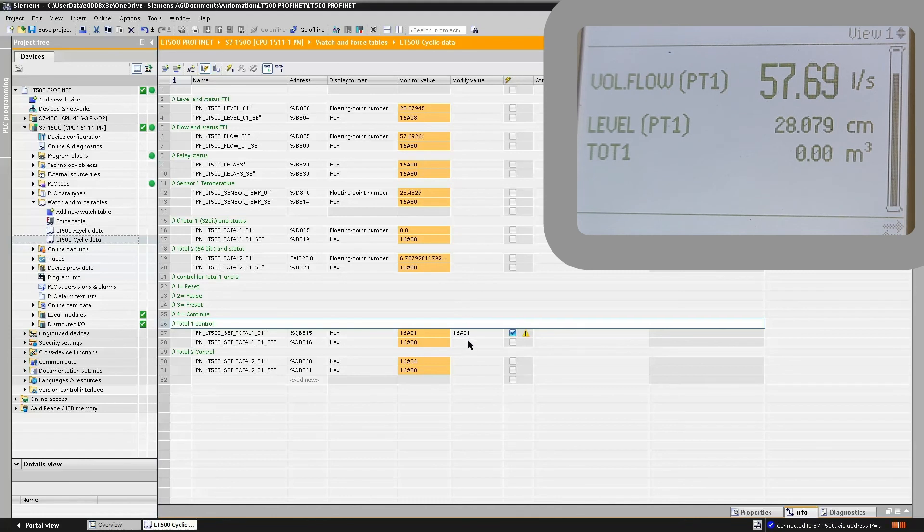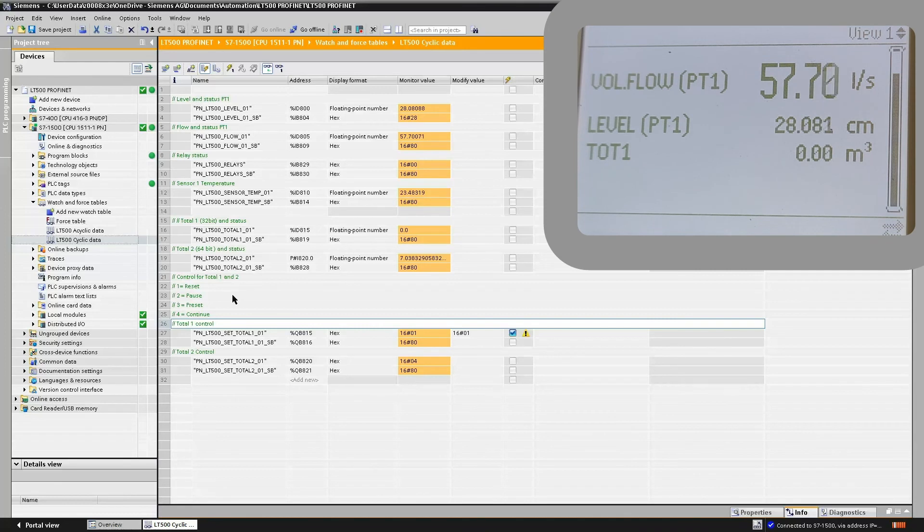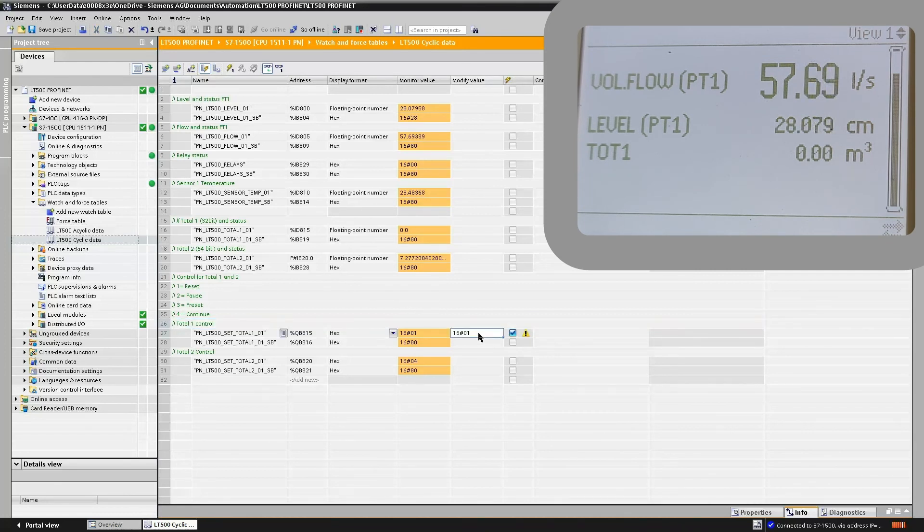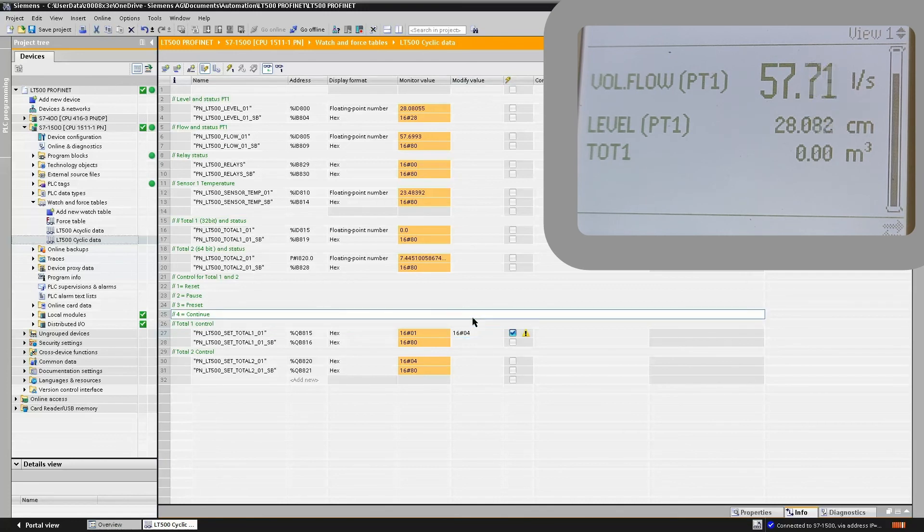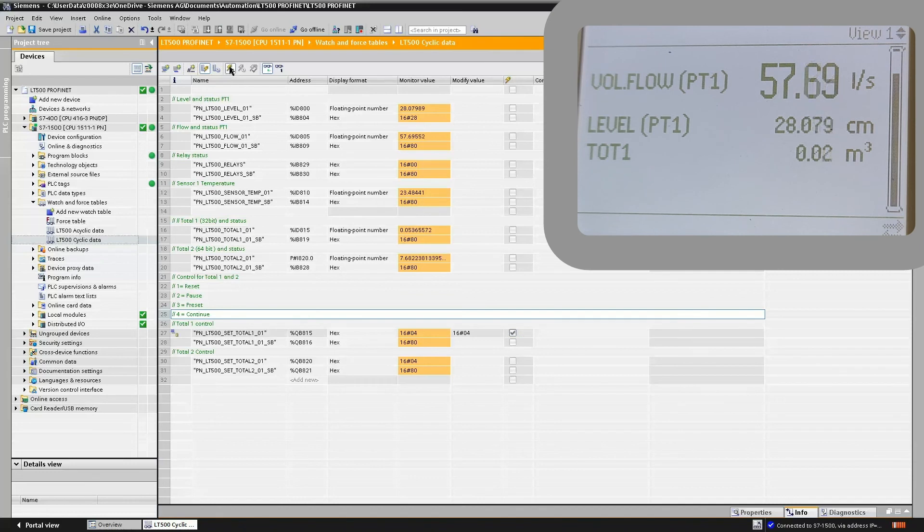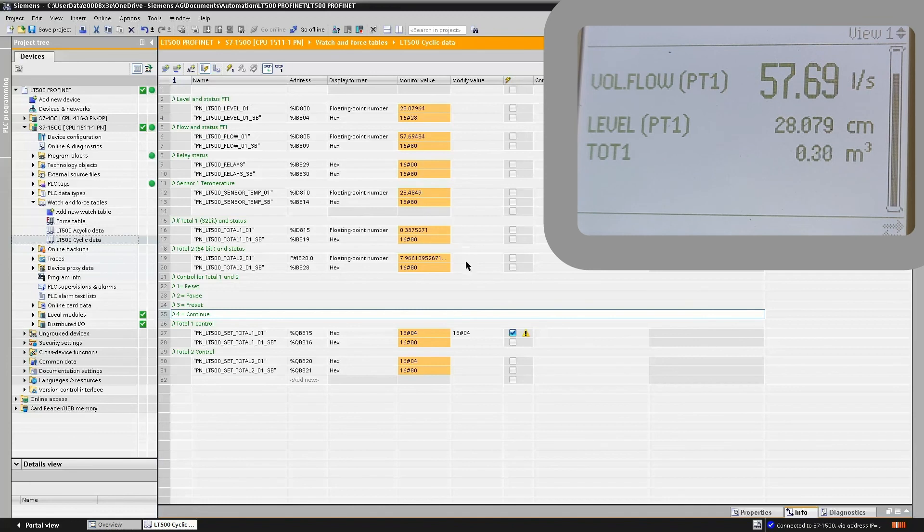To start the totalizer again, we can either pause the totalizer, preset the totalizer, stop or start the totalizer. So let's start the totalizer running by entering 4, updating our tag table, and you'll see that the totalizer now has started to increment once again.